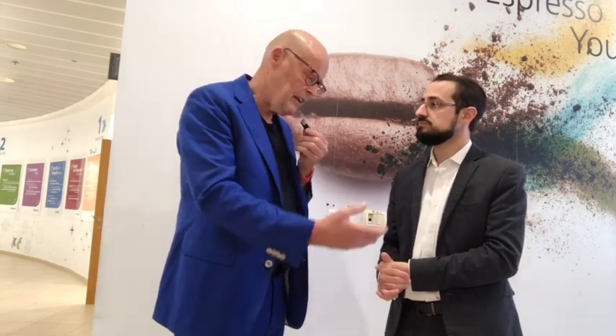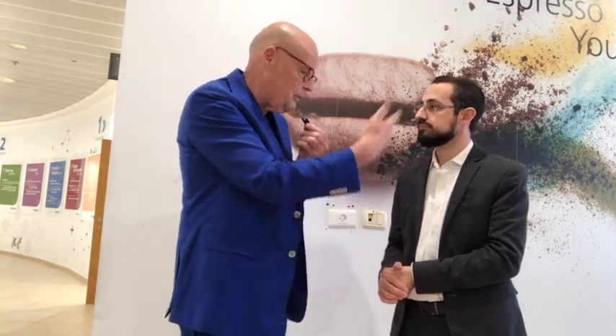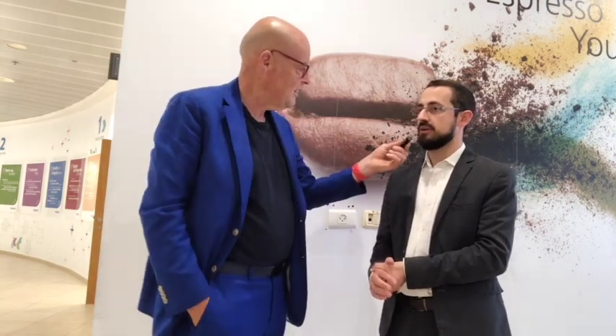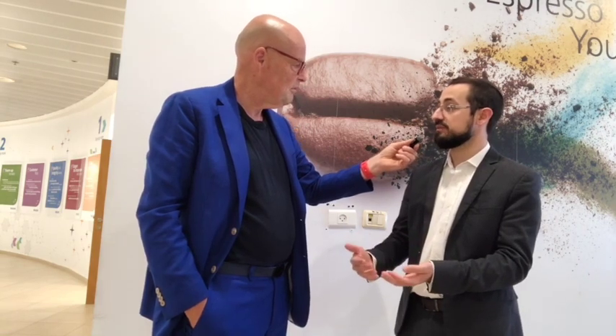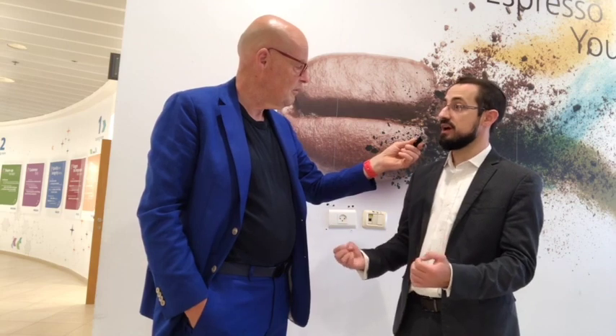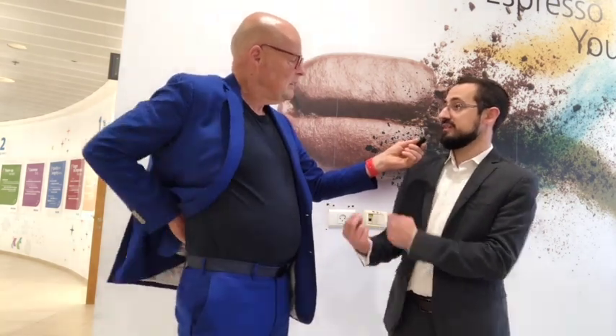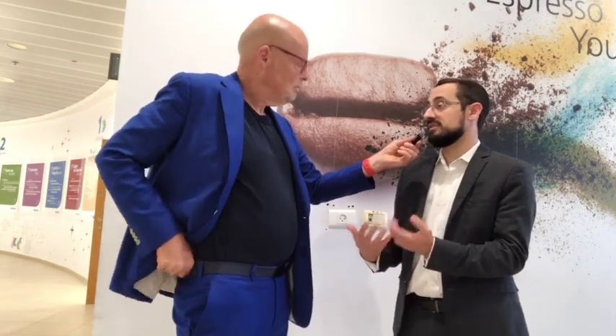So you say you're growing very fast. You have been integrated by Philips slowly, and you say it's an open system. You're also late to the market. There's a lot of competitors. What are the practical advantages of your system? And what does open mean? Okay, so open means that we are able to work with catheters that have been developed by other vendors, and we can still have advanced features like evaluation of ablation catheter contact with the tissue without having any technology built into the catheter, because it's built into the system.